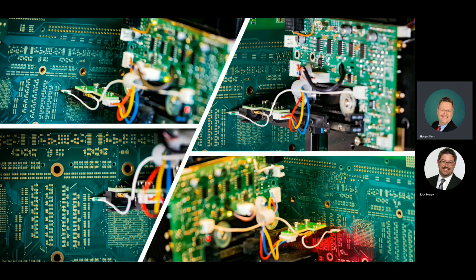When we don't get this signal in time as expected, we know we may have a wrong contact, the probe hit somewhere else, resulting in an open, or we're in the wrong location, which also creates an open or an error. We also control the movements so we're really sure when we make a measurement, we did a measurement. If we didn't get a result back, we can tell that something is wrong.